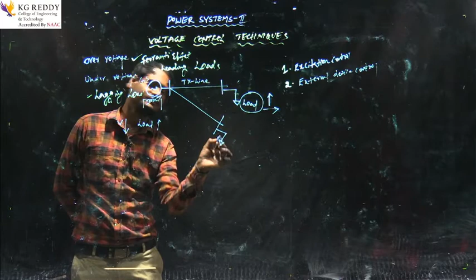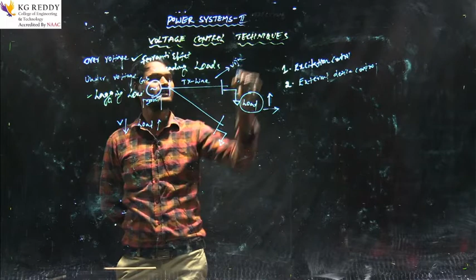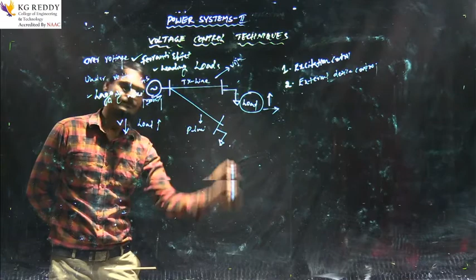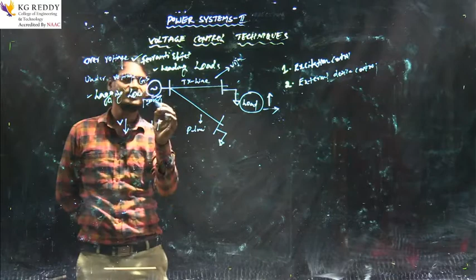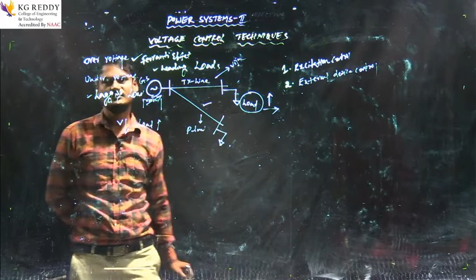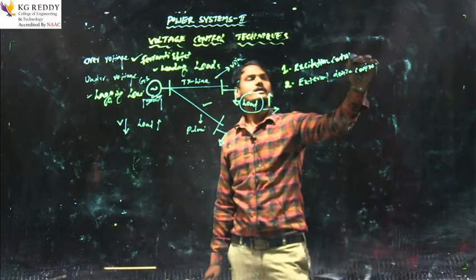But when excitation changes, there are also other bus bars, right? For example, if you consider this a Vijayawada transmission line and that a Palvancha transmission line, what will happen? If I change the excitation, the Vijayawada transmission line will maintain a constant voltage. Why? Because here the voltage has increased, I need to balance this, so I have changed this excitation, and the voltage maintains constant. But unfortunately, in the Palvancha transmission line there is no voltage change. So if I change the excitation in the power plant, this bus bar will get affected. This is one major drawback of the excitation control method.